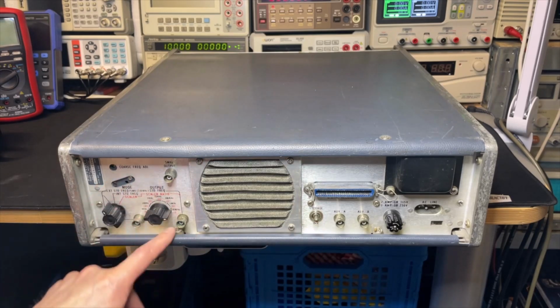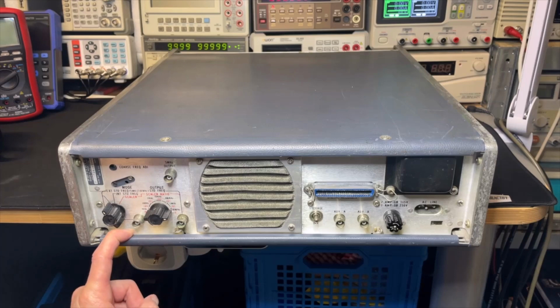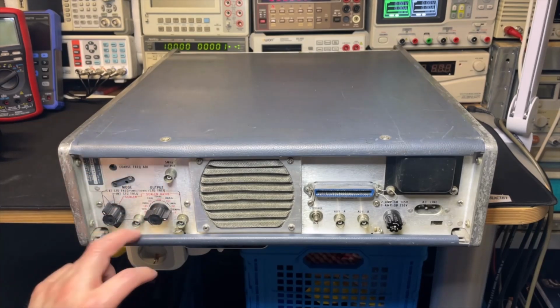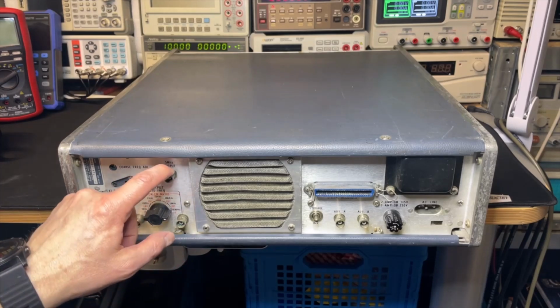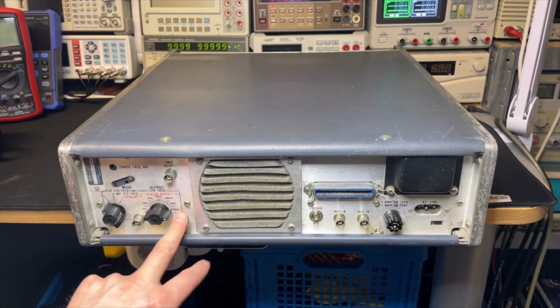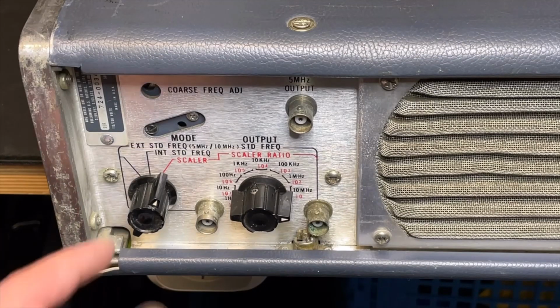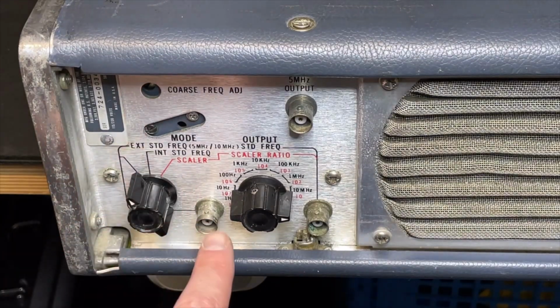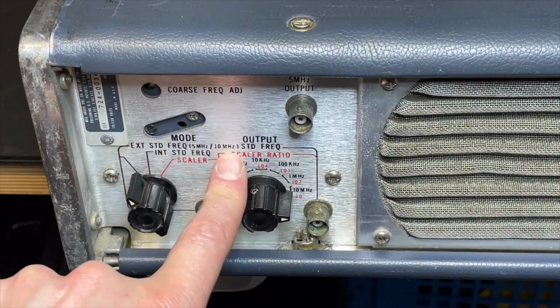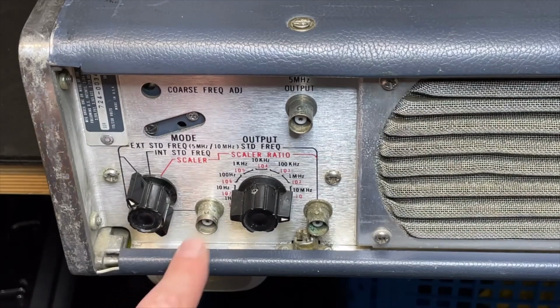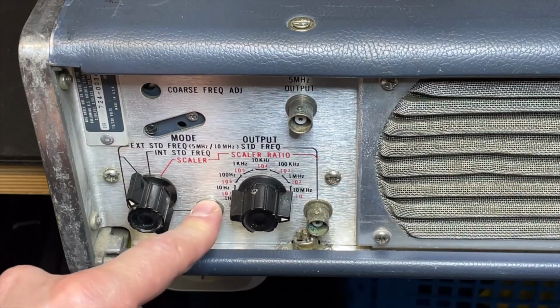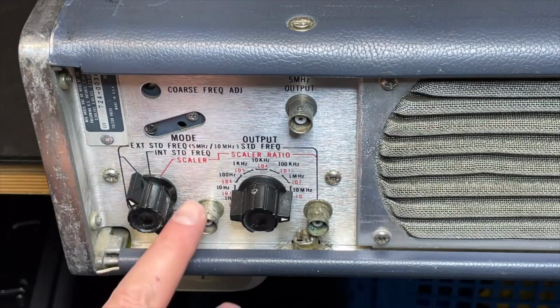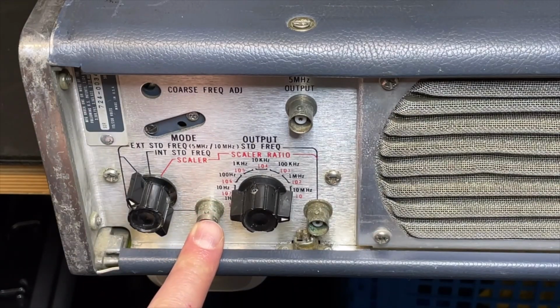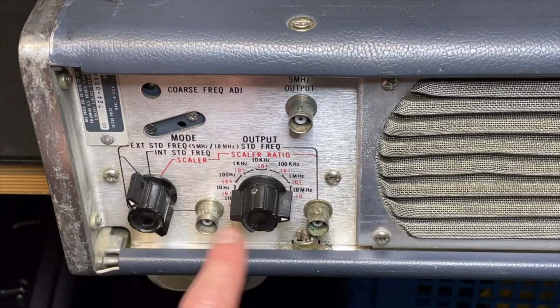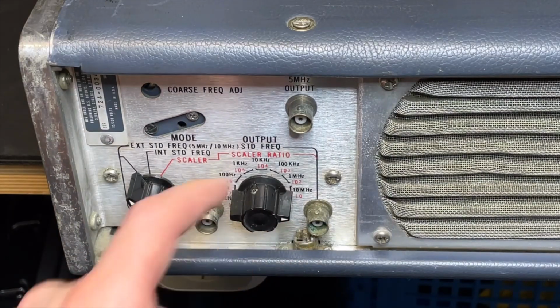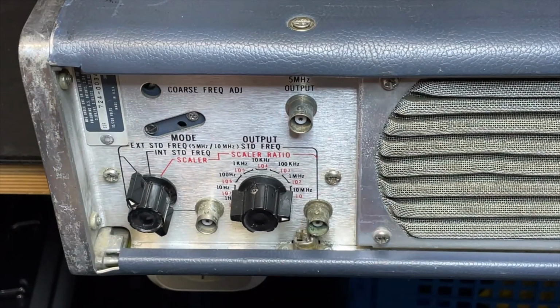And this is also an extra on the M version, that it has a scaler, while on the L version you can only input 1 megahertz. Here you can also put 10. Now it even seems that if you set it to external, you can enter input 5 or 10. It doesn't matter, it will figure it out itself. With all the old counters it usually was 5, 2 or 1. And I think with the L version it was even only 1 megahertz. And now you could even use the scaler. So when I input 10 megahertz here, I can even use the scaler to output to another device.